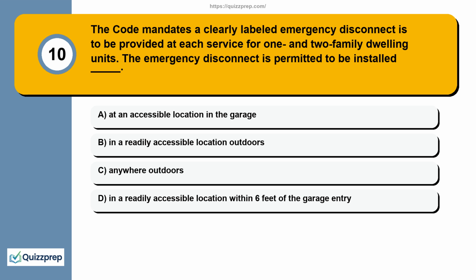Question 10. The code mandates a clearly labeled emergency disconnect to be provided at each service for 1 and 2 family dwelling units. The emergency disconnect is permitted to be installed at an accessible location in the garage, in a readily accessible location outdoors, anywhere outdoors, in a readily accessible location within 6 feet of the garage entry.